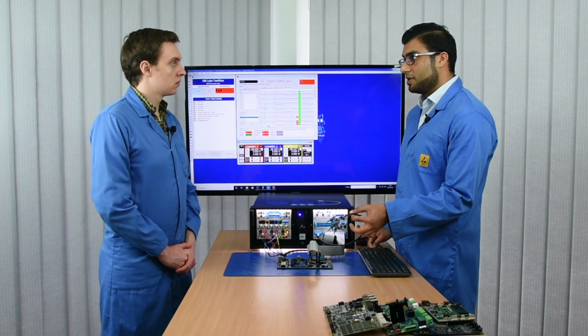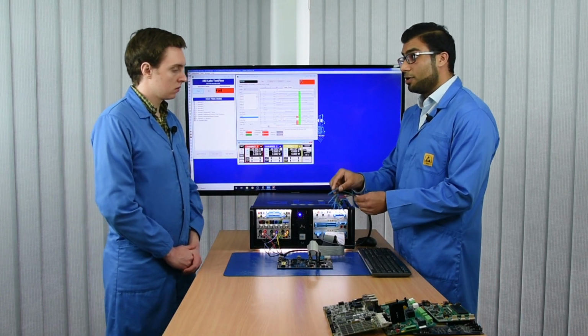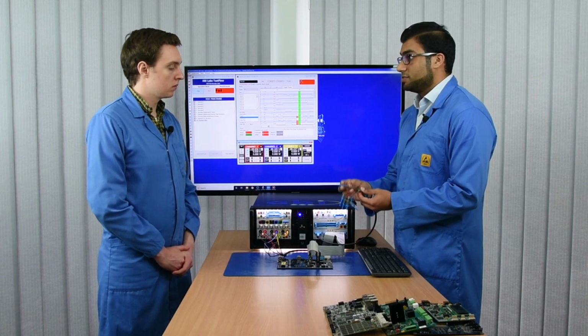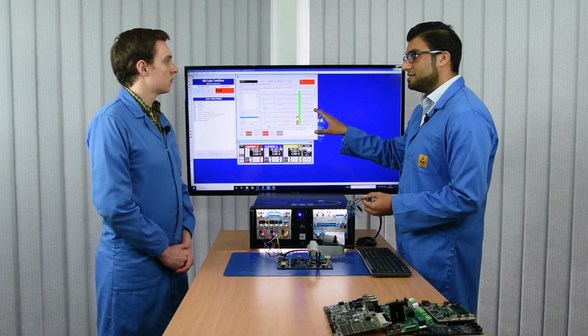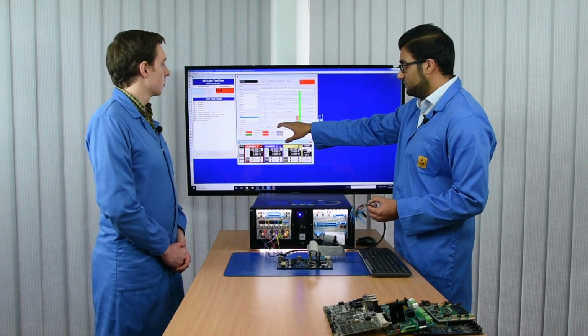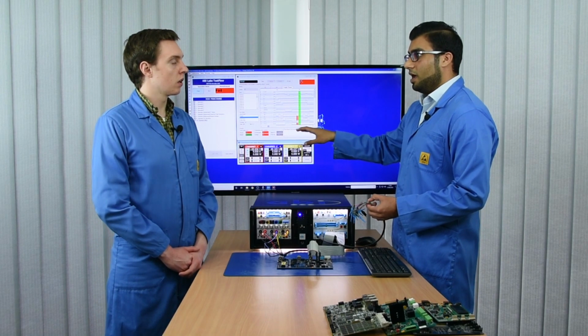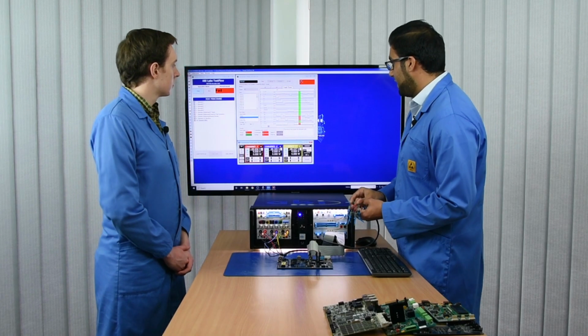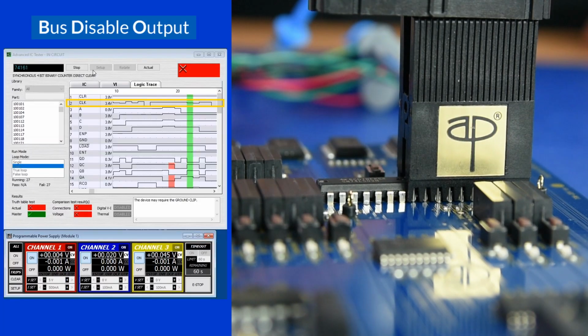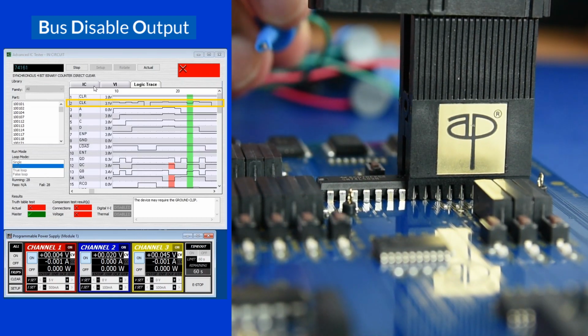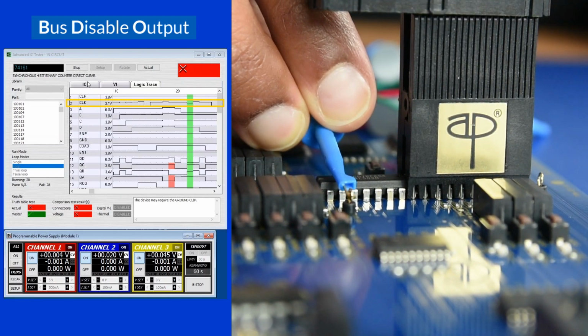So what would we do about that? Okay, so as I mentioned, we use a BDO cable. In this example, we're going to send a low signal to disable this clock, to stabilize our IC. And as you can see, the truth table is failing, connection and voltage are failing. So we need to stabilize it before we can do those specific tests. Okay, so if you keep an eye on the test itself. Now that the cable's connected, we will see that everything should pass in a second, just like that.